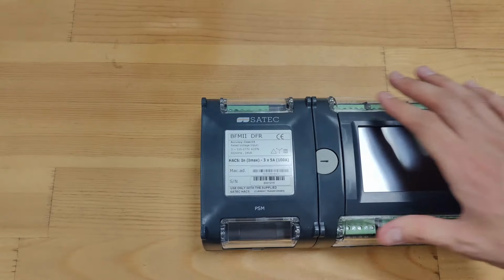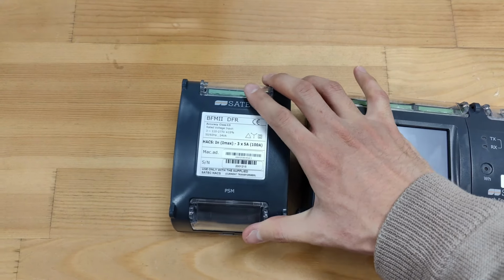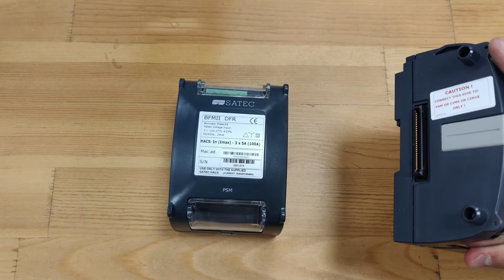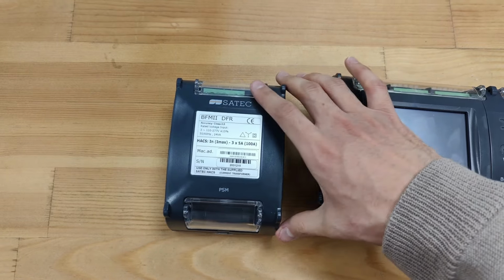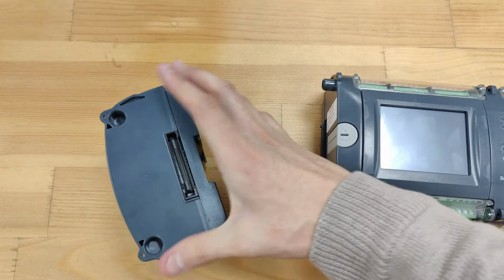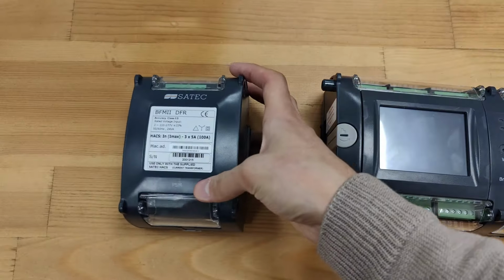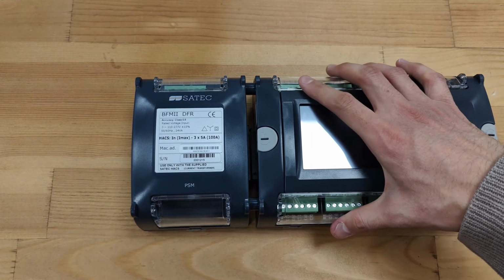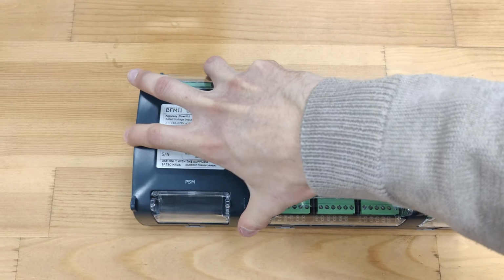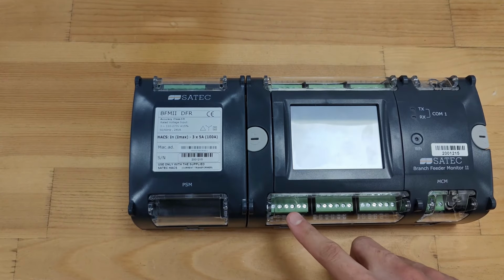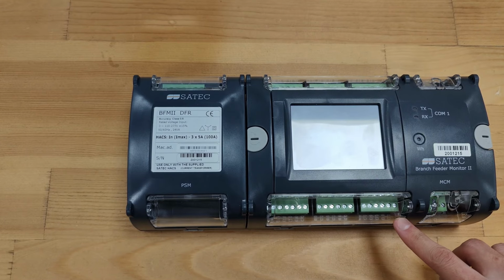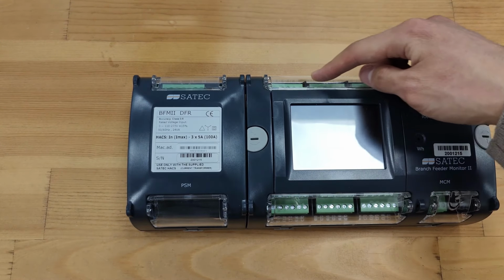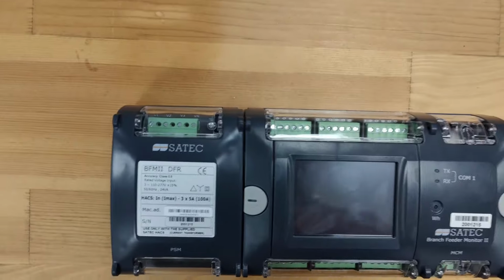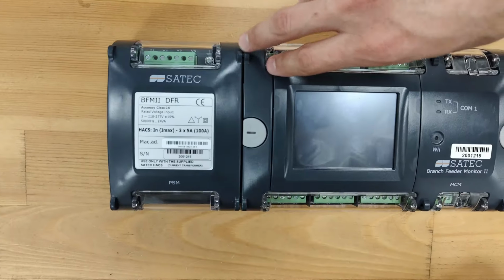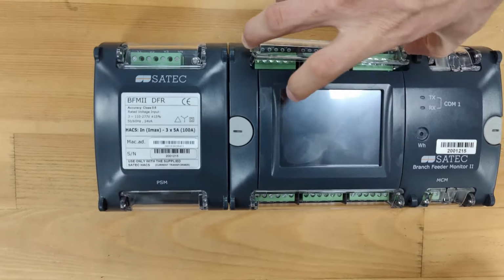As you may have noticed, this device is modular. The connection is realized by means of a side loop installed on the device parts. Later we will consider the connection of additional modules. As I have already mentioned, this device allows simultaneous monitoring of power grid parameters. Here you can see the terminals to which current circuits are directly connected. As you can see, 18 single-phase or 6 three-phase consumers can be connected.